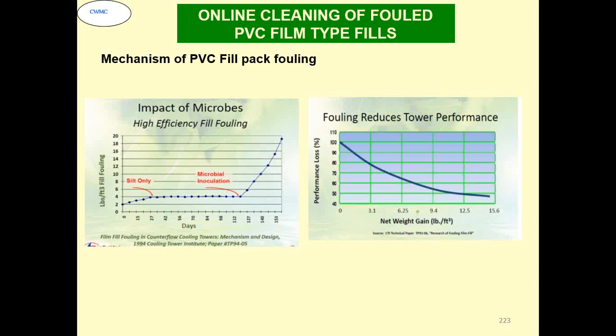airborne dust. People have a feeling that it is water related, but normally the water side problem is lesser. Unless we have no treatment, no clarifier, and we are using direct water, then yes, it has an effect. Otherwise, airborne dust normally has more effect than clarified water. As the fouling increases, tower performance reduces.